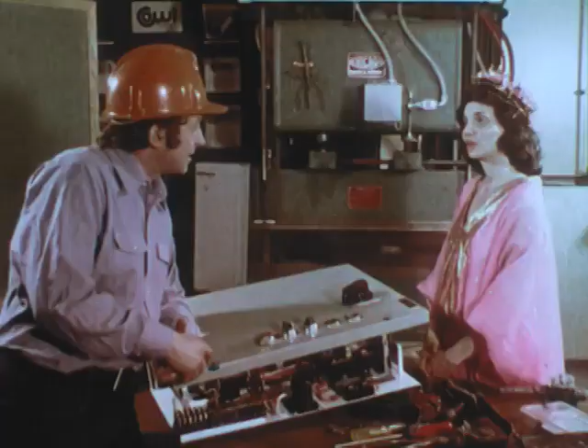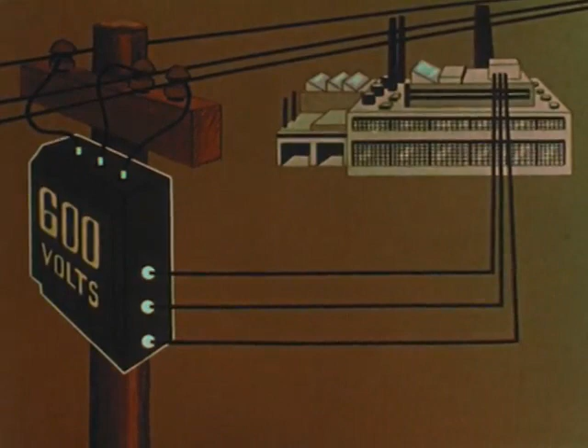Say, do you know what a delta circuit is? Uh-uh. It's a three-phase circuit. And if you remember, many flashes and fires are caused by a ground fault in a three-phase circuit. The current for an ungrounded delta or three-phase circuit is supplied from a three-phase transformer. A voltmeter connected between any phase and ground will read about 347 volts if the circuit is functioning normally. In a circuit that is functioning normally, the voltage phase to phase, in this case, is 600 volts.